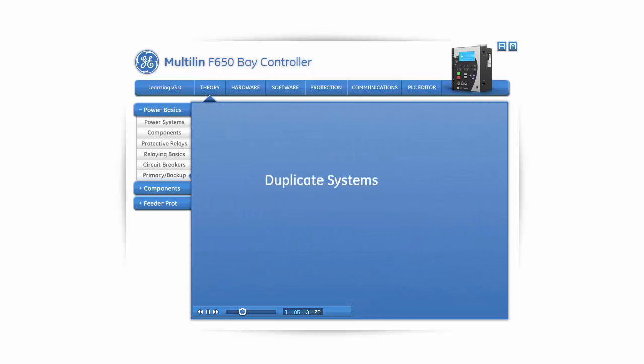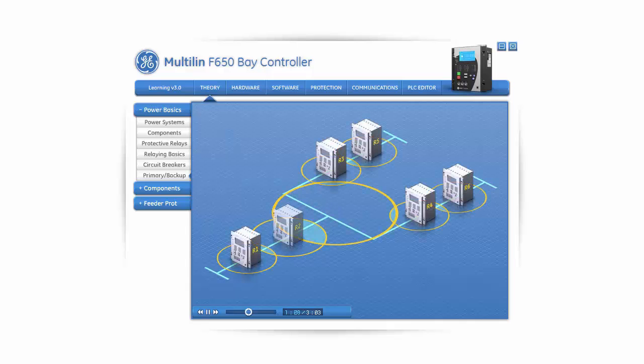Duplicate systems. On high-voltage systems, it is a common practice to duplicate the protection systems to ensure proper operation if a failure occurs. In some cases, only the relays are duplicated, while in other cases, the entire protection system is duplicated. This is the preferred choice when economically justifiable. Let's take a look at several backup strategies being used within one power system transmission line.